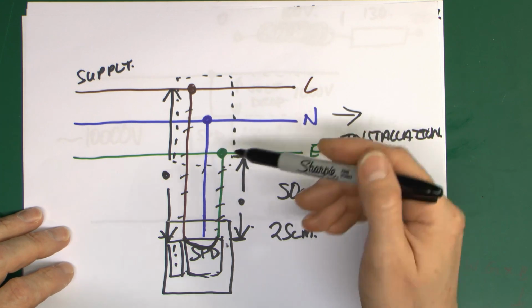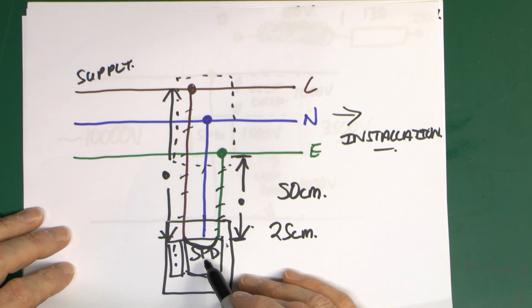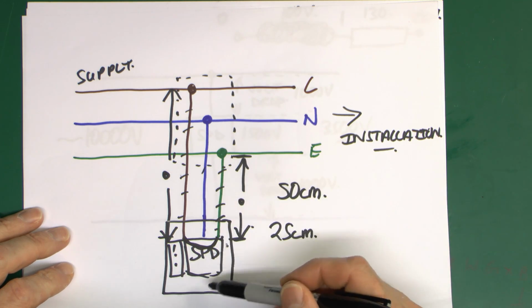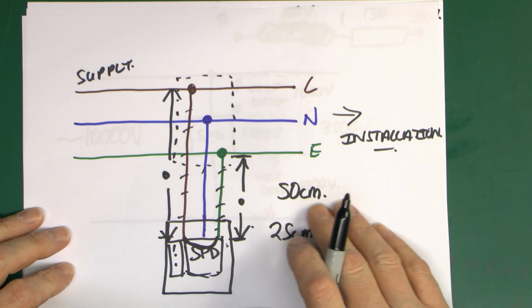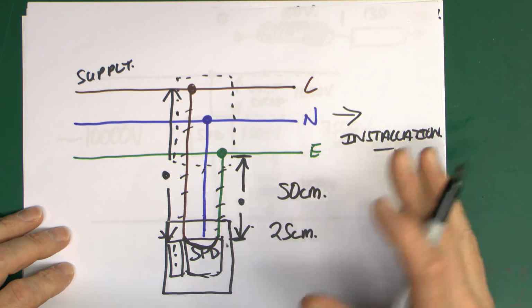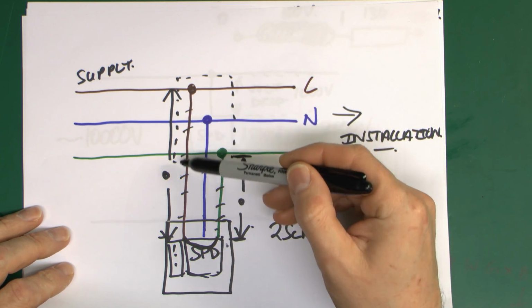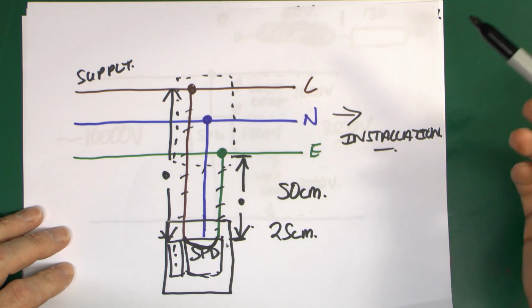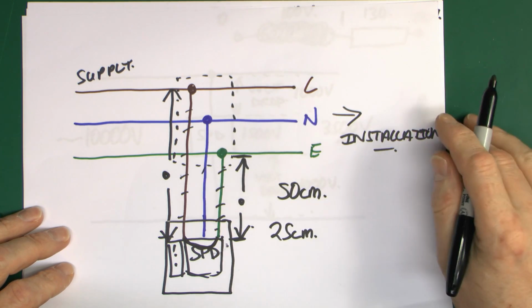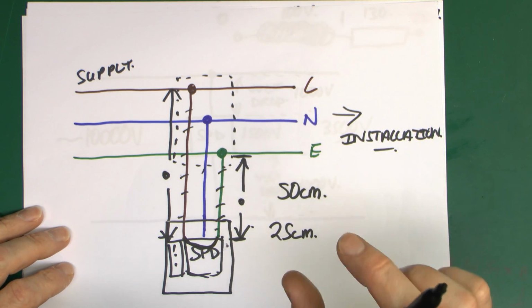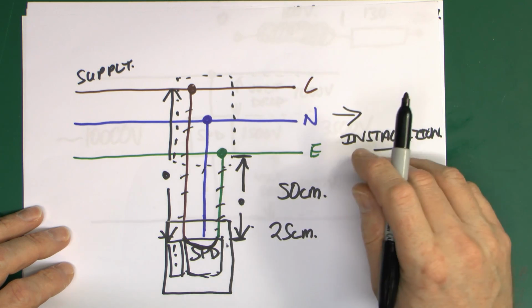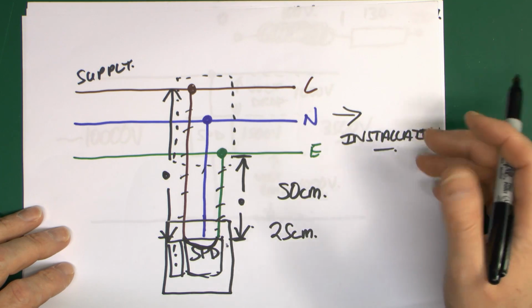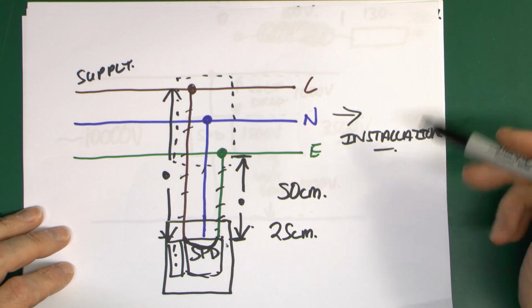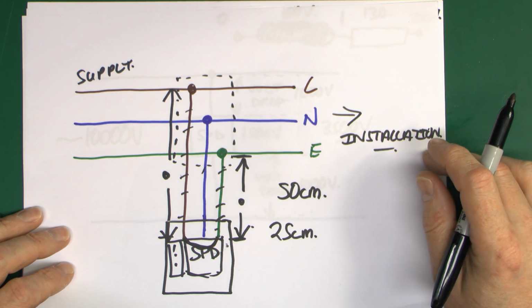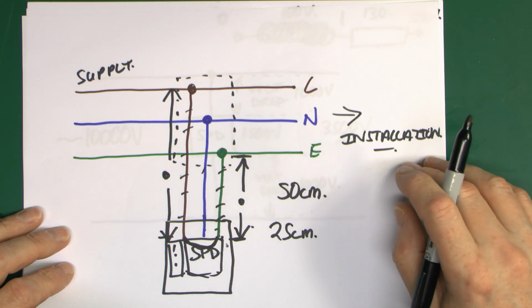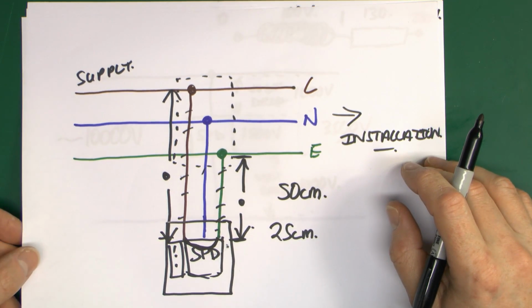If you start out at 0, the surge protection device is as effective as it can be, and as these get longer it gets less and less effective. So really it's not about thinking about, say, 50 centimeters or less. It should be about making these as absolutely short as you possibly can. And say one way to do it, say with that Wylex example we saw earlier, just having those extremely short little bars underneath, literally in the order of 2 or 3 centimeters or something. So shorter is always better. The 50 centimeters or the meter listed in the regulations is really an absolute maximum, and you don't really want to be getting anywhere near that.